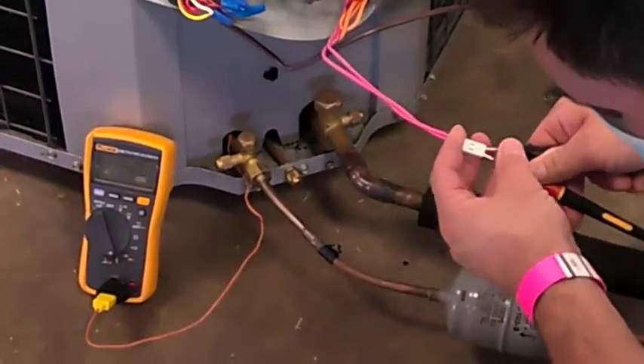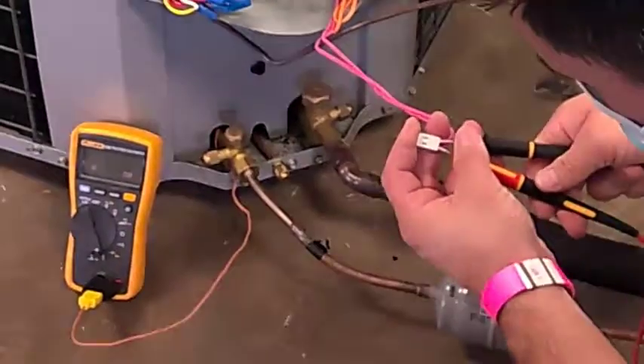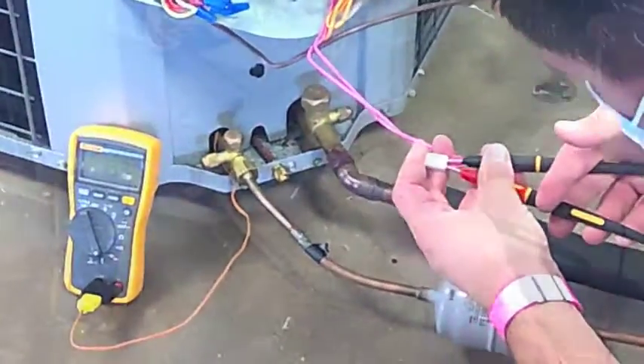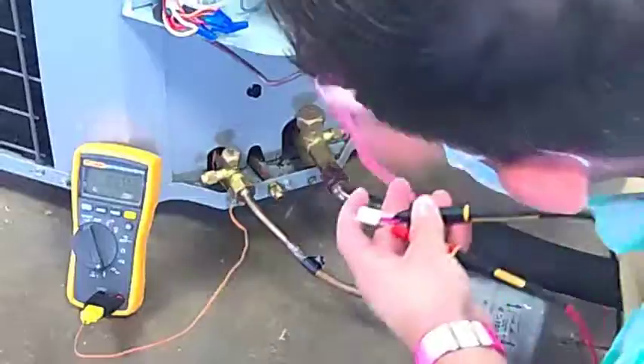Continuing to drop. So we're down to 14 degrees and the switch is still not closed yet. You can see we're starting to accumulate a good bit of frost on the outside of our coil now.